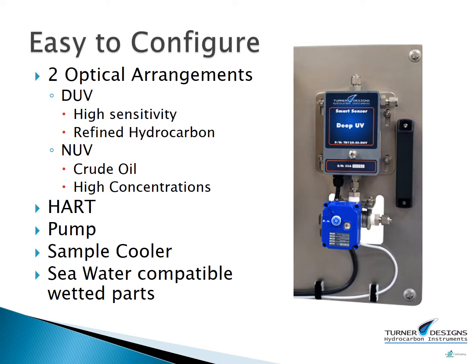Ordering and specifying a TD120 is quite simple. There are only two optical configurations available, the deep UV and the near UV. Deep UV is for measurement of refined hydrocarbons or applications that need the highest sensitivity available. The near UV is for measuring crude oils or heavy fuels and the highest concentrations available.